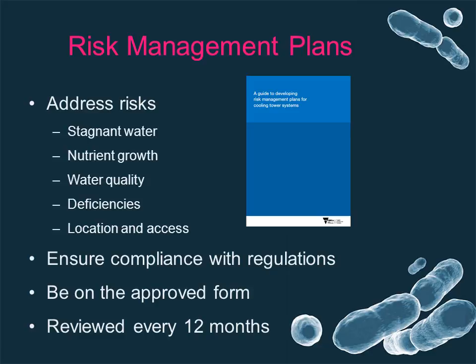Risk management plans must address specific risks, including stagnant water, nutrient growth, appropriate water quality, deficiencies within the cooling tower operational maintenance, as well as list the location and how the cooling tower can be accessed. This is to ensure compliance with the appropriate regulations, and risk management plans are to be completed on an approved form and reviewed every 12 months.